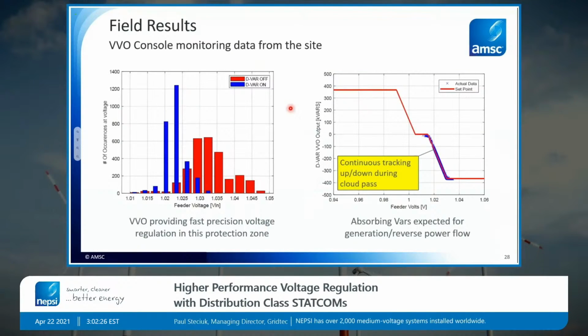Here's some data that was taken during a partly cloudy day now, and what we're seeing here is the tracking performance of the STATCOM device. So this is configured in a VAR mode, and on that feeder, it's primarily acting in the inductive range, and that's not surprising because we're trying to pull down the voltage. As that solar is trying to push it up, we use the inductive capacity to pull it down, and then as the clouds pass, it would very rapidly ramp up and down this curve as those variabilities are occurring. And on the left, we see a histogram of the VVO.